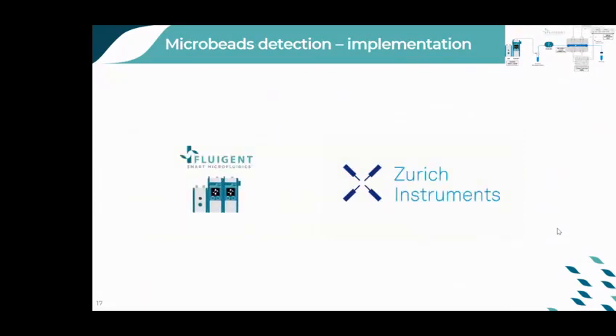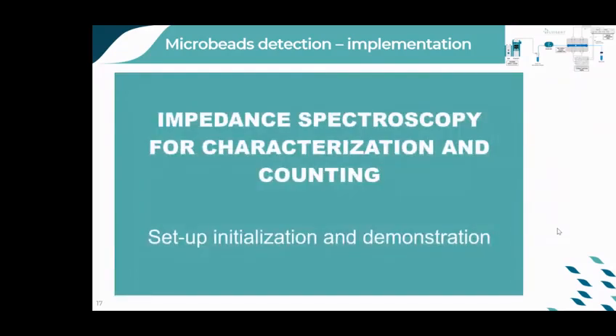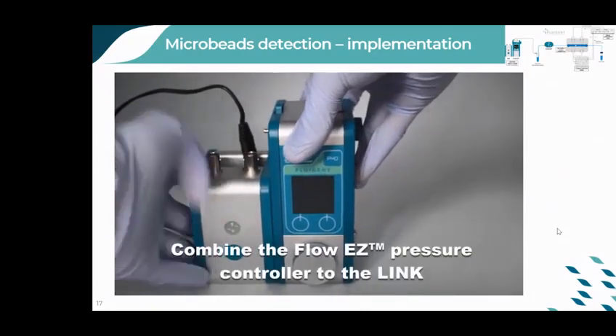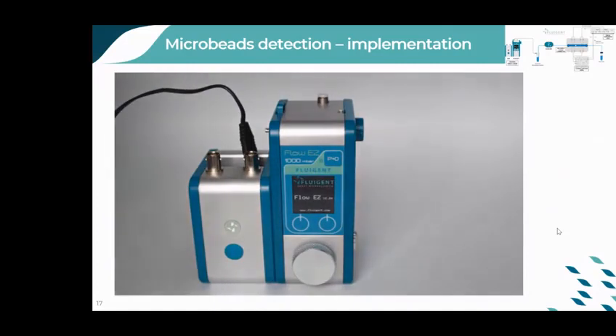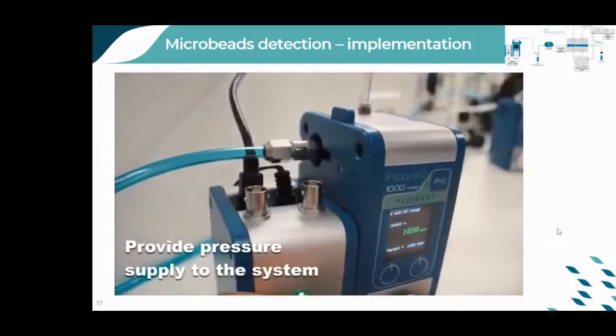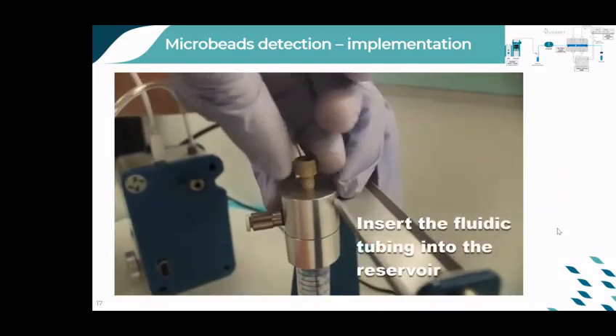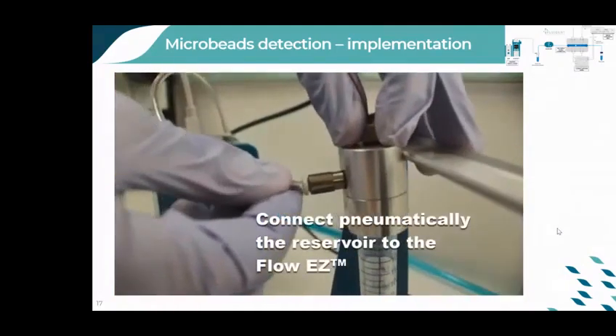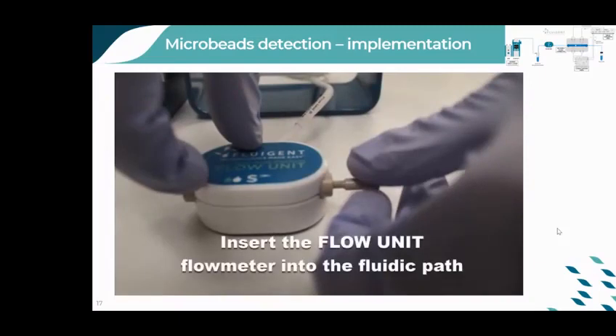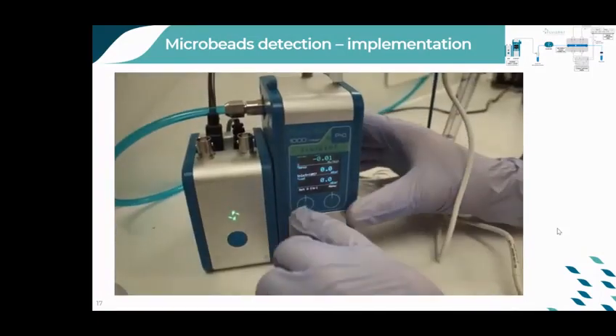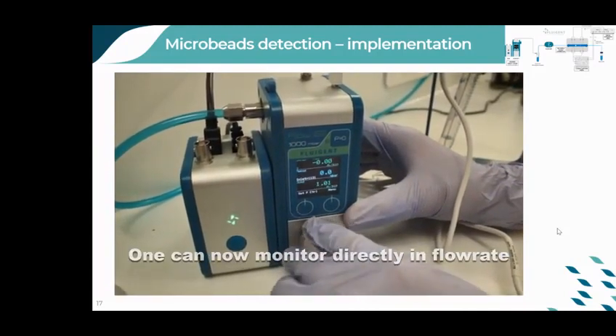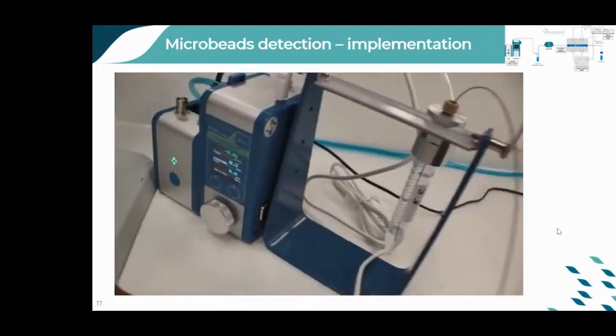We also thought it could be useful to show you how we really set up the platform, so we made a video of the setup implementation with real measurements. As we saw in the scheme, you first need to connect the Flow EZ to the Link for power supply, and more importantly, to allow access to our software. You can next provide the pressure supply to the system and connect the Flow EZ to the reservoir. The tubing is connected to the reservoir and passes through a flow unit, which permits to switch from pressure control to flow rate control. You can directly set the flow rate by using the Flow EZ dial, allowing for local control without the need of a PC. The flow control part is now ready.